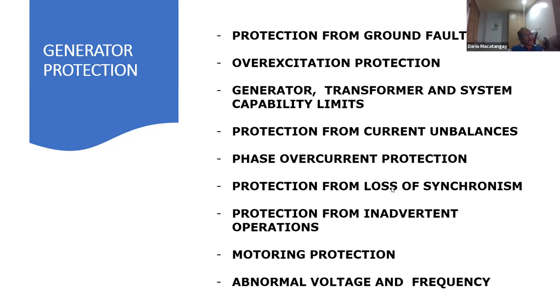Now, another thing that needs to be considered is the loss of synchronism. Again, the system and the generator are synchronized, so they're happy when they're synchronized. But if there's a fault in the system, especially if they have a big power generator, or it's a large system, and especially if the system is weak, then they have what they call a short circuit center. When you lose synchronism, you go into an unstable state, and if there's a fault in the system, the generator needs to see whether it needs to trip or not.